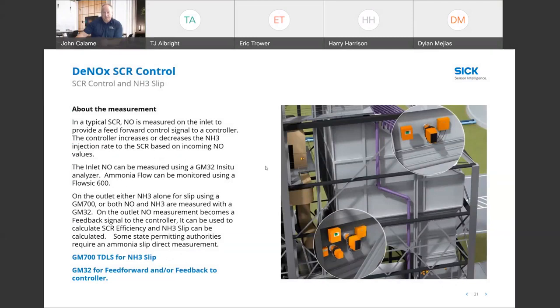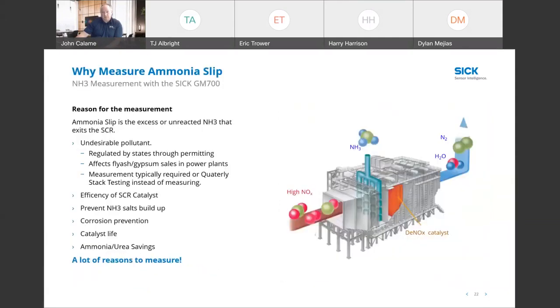The DeNOx and the SCR control shows you a typical install with our devices, where we could have the GM32 on the inlet measuring the actual NOx, and then giving a feed forward signal over to the ammonia injection, so they know what the loading is, what the NOx levels are, so you know how to adjust your ammonia feed so that you're not overfeeding. And then we can measure with the GM700, the TDL that Dylan mentioned, the ammonia slip quite accurately as well. So you know what's slipping through, and make sure you have the proper amount of ammonia. And we can give you the feed forward to optimize the control.